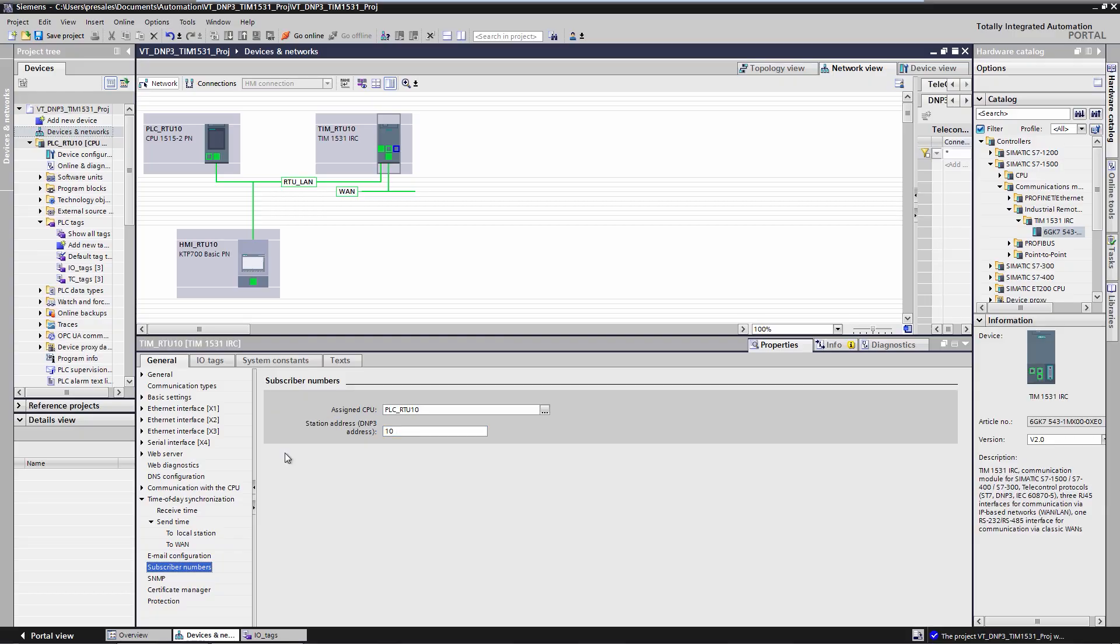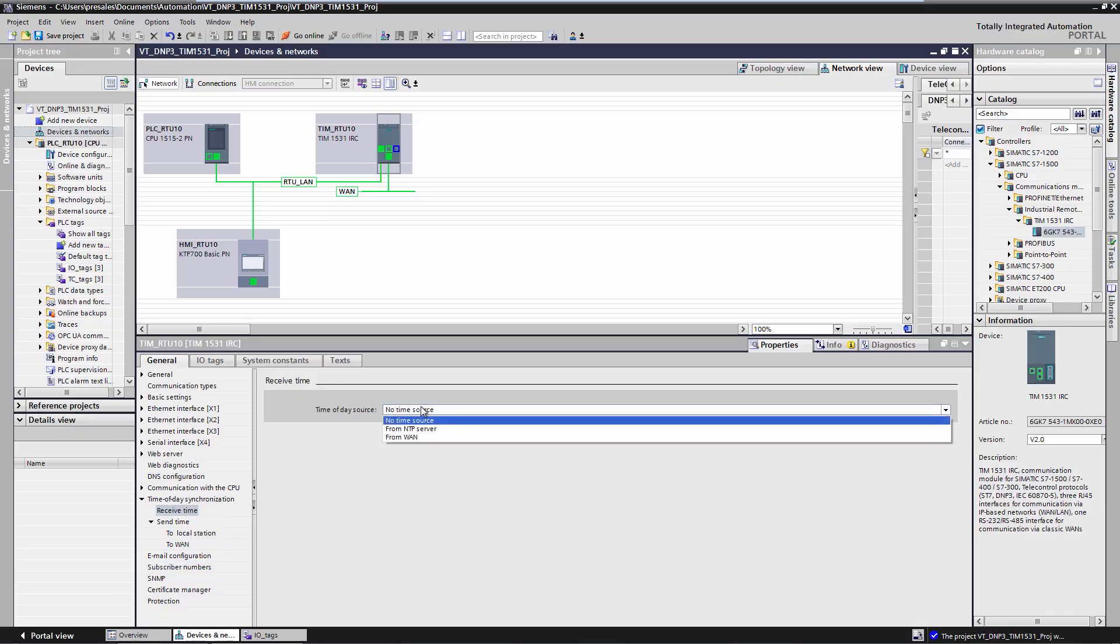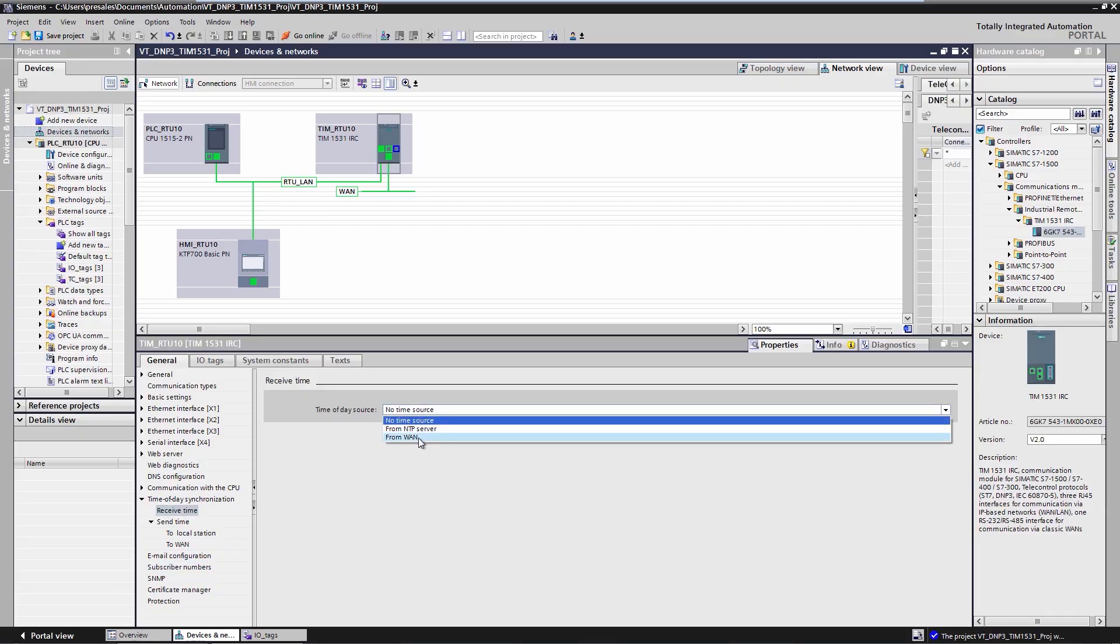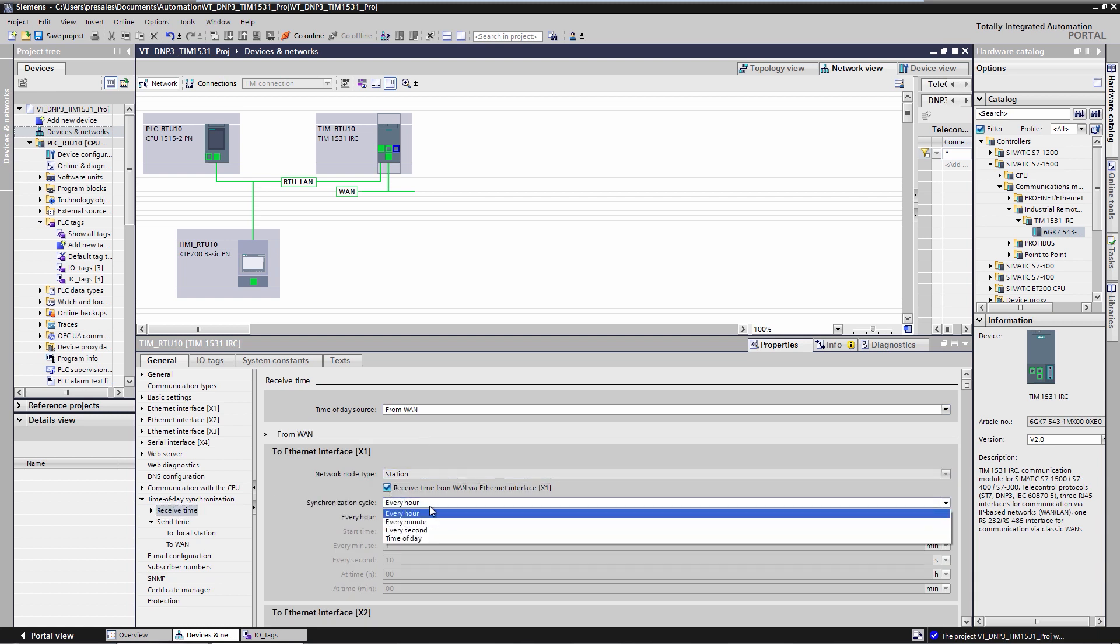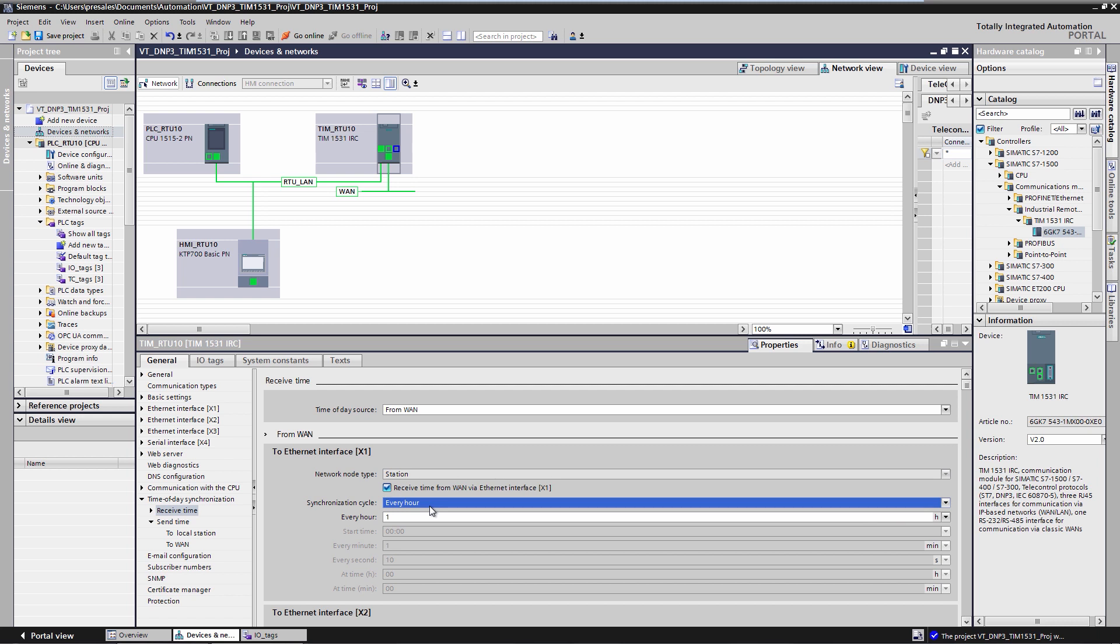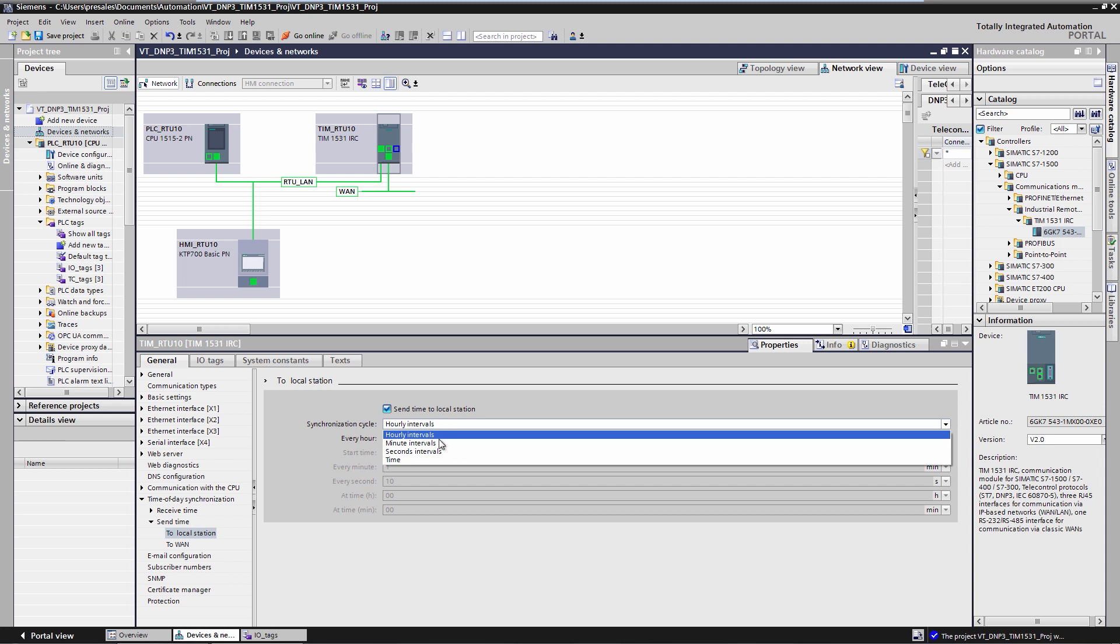In order for the DNP3 RTU to be cyclically synchronized by the master with date and time information, we configure the time synchronization in the X1 interface, which is the interface to the DNP3 master. Receive time via WAN in the X1 interface in the time grid of once per hour. If we also want to pass on the time received from the master to the CPU, we configure a synchronization grid for the X3 interface to the CPU. Send time to local station in the minute grid.